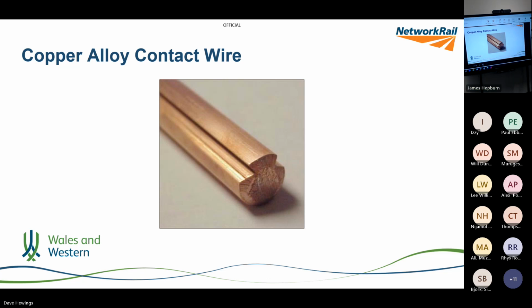Now, an old law of overhead line design is to try not to bring copper and aluminium together. The electrochemical series of copper and aluminium means that if there's electrolytic action - something to carry ions between copper and aluminium - you risk the copper degrading the aluminium, with the aluminium sacrificed for the copper. But it's been used very successfully in many tunnels around the world, and that hasn't really been an issue. There's also grease applied in the groove that helps keep the electrochemical action at bay.